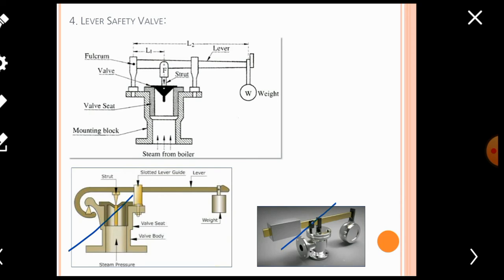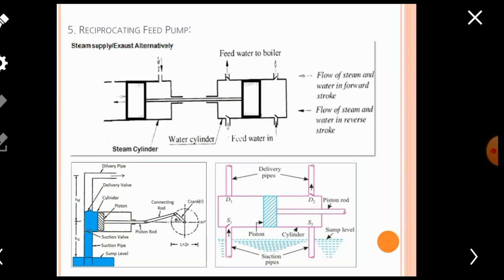The fifth type of boiler mounting is the reciprocating feed pump. In medium-pressure, high-pressure, or supercritical boilers, a large quantity of water is needed. In low-pressure boilers water enters the boiler shell by gravitational force, but in large-capacity boilers where large amounts of power need to be produced, water must be pumped forcefully inside the boiler shell. The mounting used for feeding or pumping large quantities of water into the boiler shell is the feed pump.